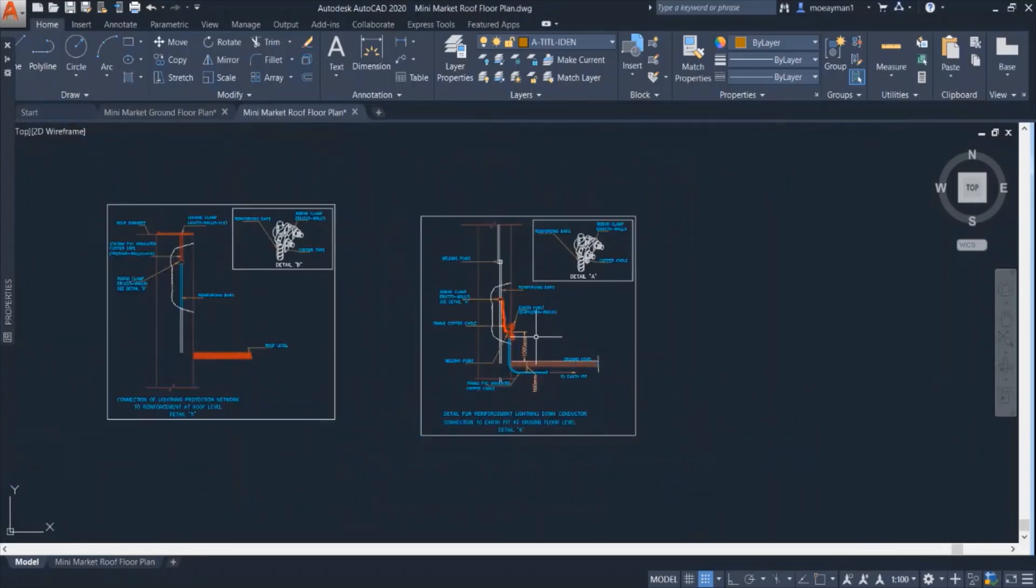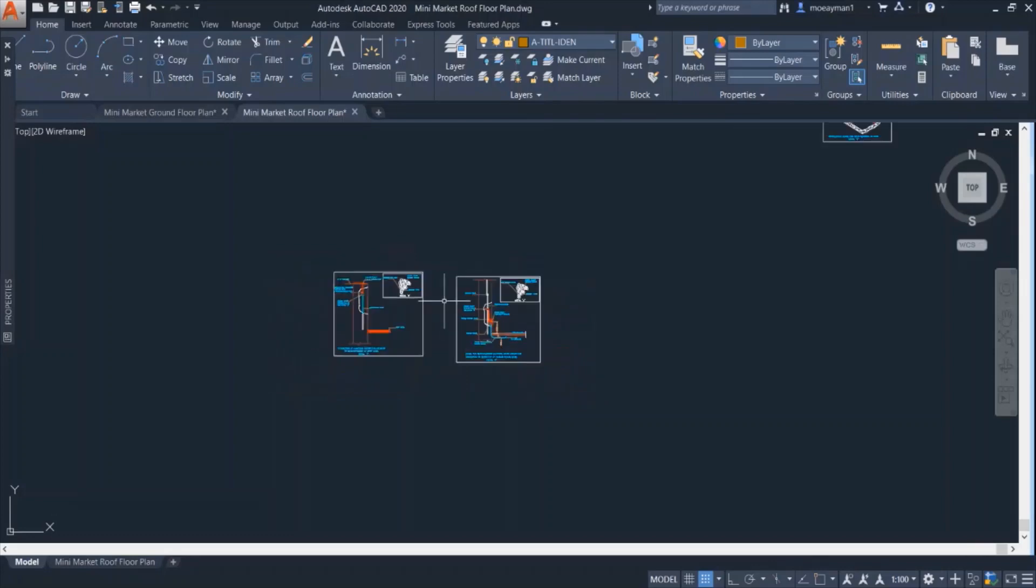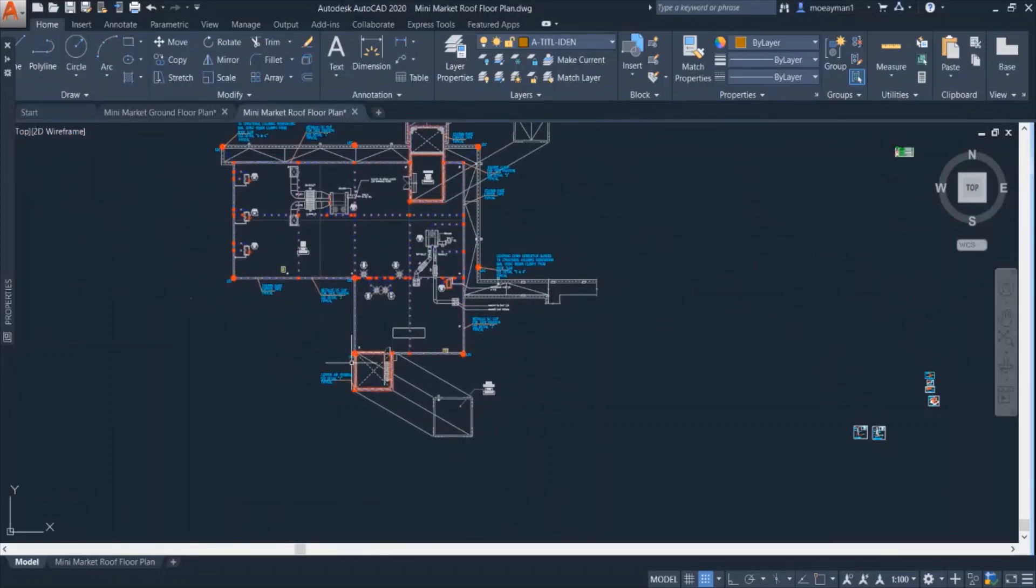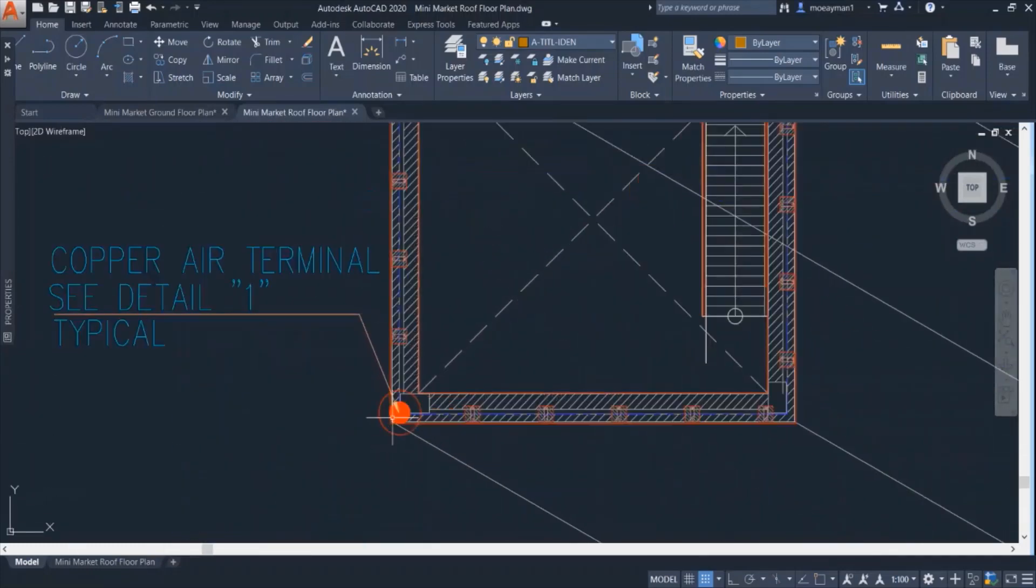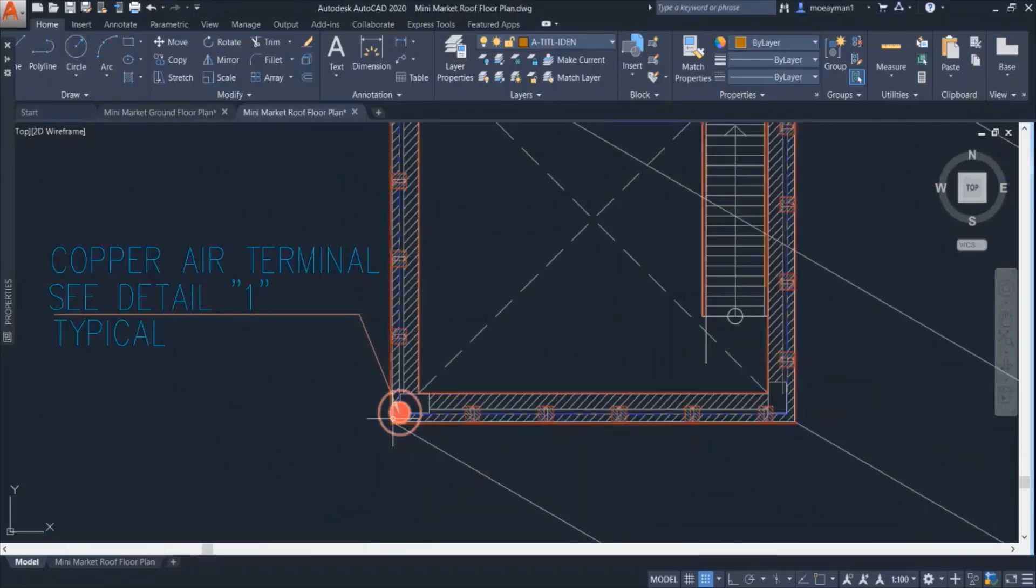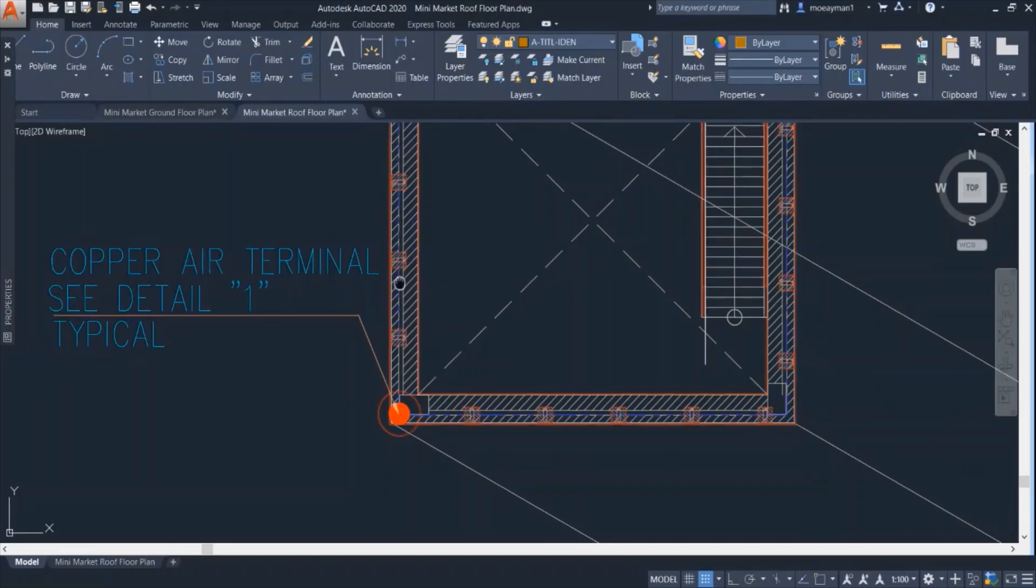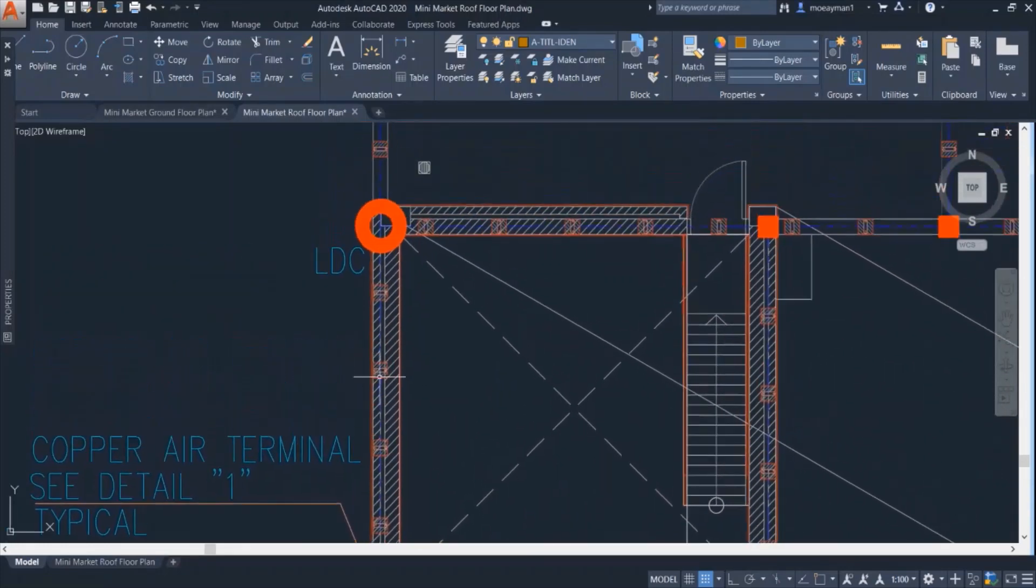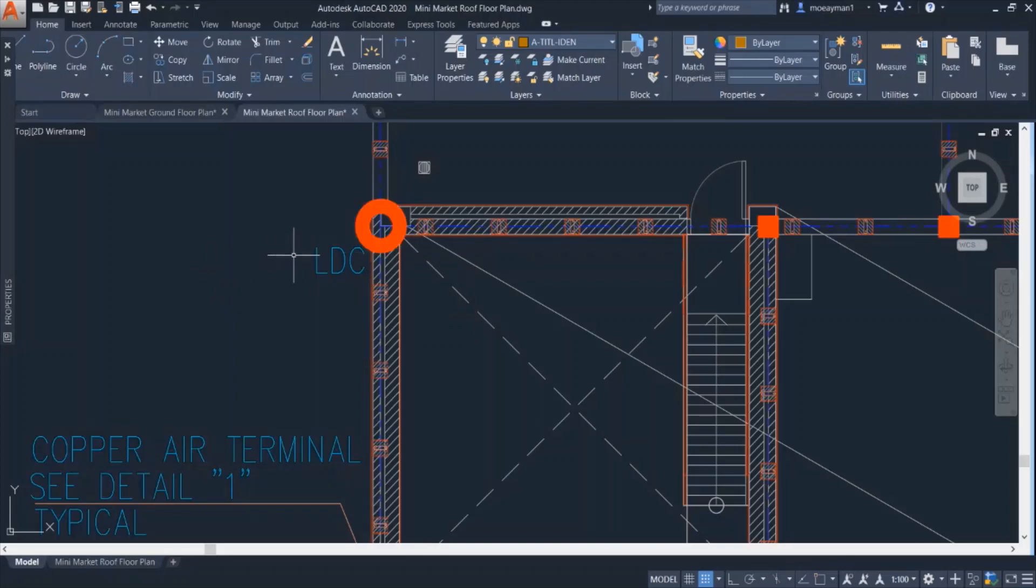I think using these details made it clear enough for us to know the real installation of lightning and earth system at the site. So during a lightning strike, the air terminal will capture the strike, then discharge it through these copper tapes, which are connected to several down conductors, that will take this huge current and voltage down to the earth pit to eventually be discharged in the ground. This is the simple explanation of the working principle of lightning system.